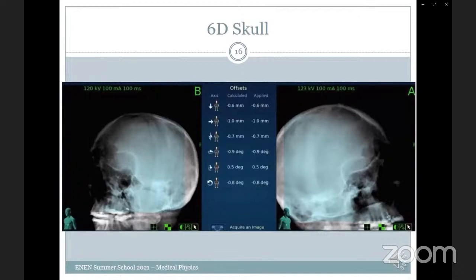Here you see an image pair with 6D skull tracking. In the background, the grayscale image is the DRR, the digitally reconstructed radiograph image coming from the planning system. So the grayscale image is the expected perfect position of the patient, where the patient should be. And the blue scale images, the live images, are acquired by the X-ray sources and detectors. So this is the actual position of the patient. And with image fusion, the system automatically calculates the offset, the differences between the expected and the live image. As you can see on the left column, this is the calculated offset. And as you see on the right column, the applied offsets are the same. So this is the correction values that are delivered by the robotic arm. So the beam is coming for the perfect position of the patient.